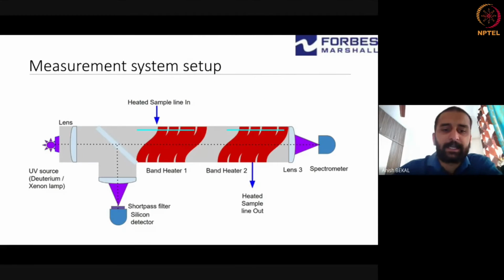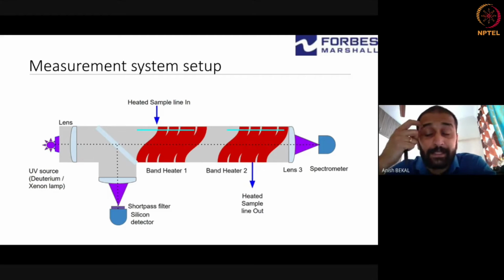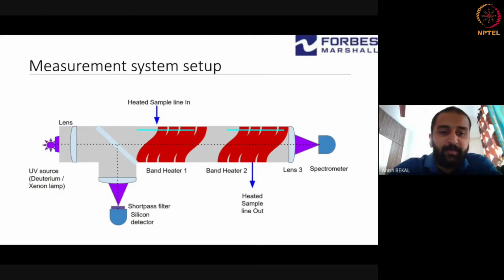So typically, how is the setup? Typically you have a source, a UV source. A UV source is typically either a deuterium lamp or a xenon lamp. Deuterium, as you know, is an isotope of hydrogen, which when excited with a heater and with the electrodes would end up emitting in the UV spectral region. And then also you have xenon lamps, which also emit in this region. So the light would pass through a heated chamber, where you have the sampled gas coming in, and this heated chamber would give you the spectra.